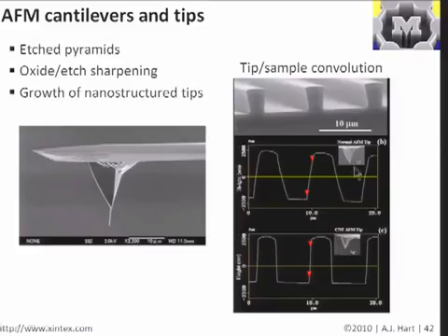And here, if you use the normal tip, you see the walls appear slanted because you have the slanted surface of the tip interacting with a straight wall, and you can imagine the tip kind of rides up over the wall and the signal looks crooked. However, if you have a nice straight tip, then you can get a much more accurate profile of the surface. And although this is an example really at the microscale for comparison, the same thing would apply to nanoscale features. If you had an array of nanoparticles that were spaced like so, and your tip didn't fit in between the nanoparticles, then this tip would tell you the substrate is flat, whereas this tip would tell you you have the particles like so.